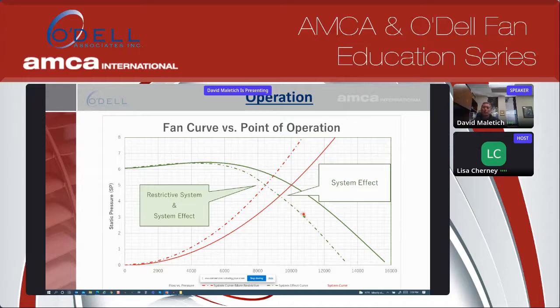It's going to make it steeper, just like if you're closing a vortex damper off, it makes the fan curve steeper. Or if you don't have a full length of ductwork on the fan, you're not allowing for the velocity profile to even out, and so consequently you have a velocity pressure loss. And that becomes more significant as the fan gets wide open, less significant as you get close to peak here. So you're changing the fan curve shape with all those other devices because they don't affect the system, but they affect how the air either enters the fan or leaves the fan. Hopefully that makes sense.